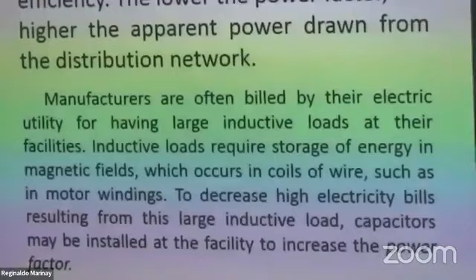So manufacturers are often billed by their electric utility for having a large inductive load at their facilities. In the Meralco franchise area, the biggest utility company in the Philippines, they have what we call a standard power factor that they have to maintain according to the Philippine Distribution Code. So we have this base power factor based on the PDC.